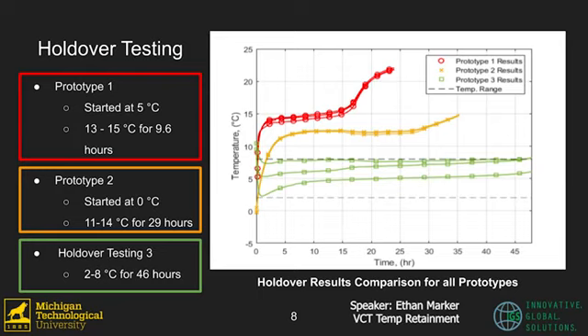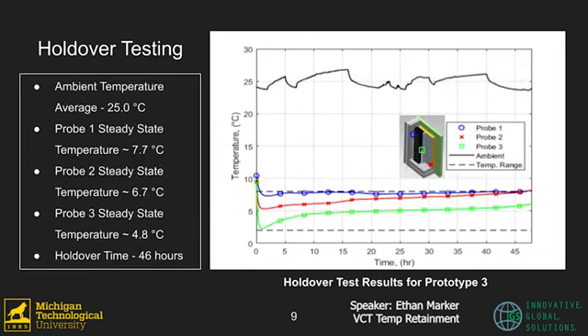Prototype 2 held a temperature range of 11 to 14 degrees Celsius for 29 hours, which also did not meet either requirement. Prototype 3 had a holdover time of 46 hours, where all 3 probes were within the allowable 2 to 8 degrees Celsius temperature range at the same time. This exceeded our design requirement by 16 hours.